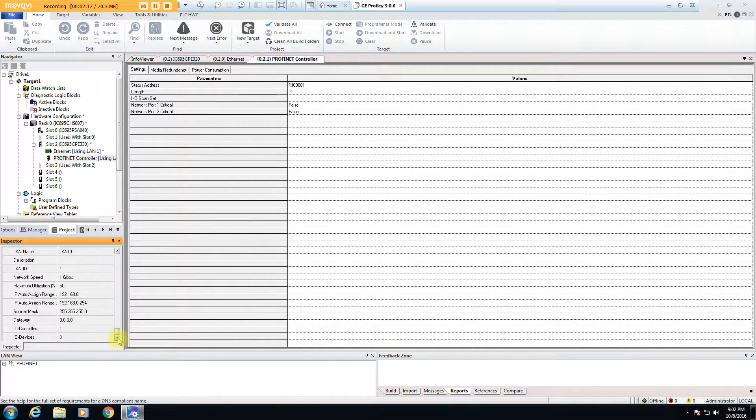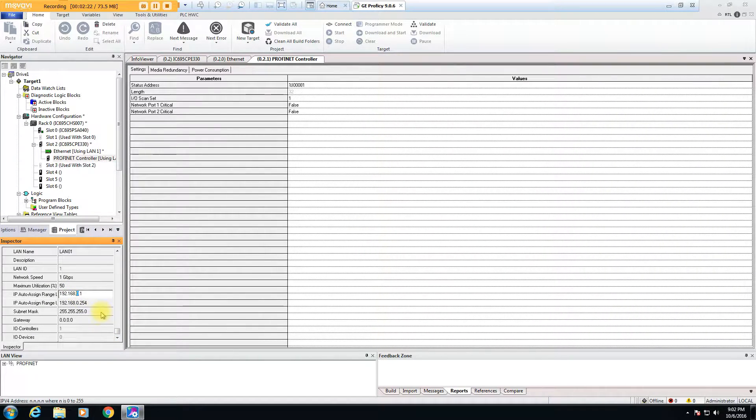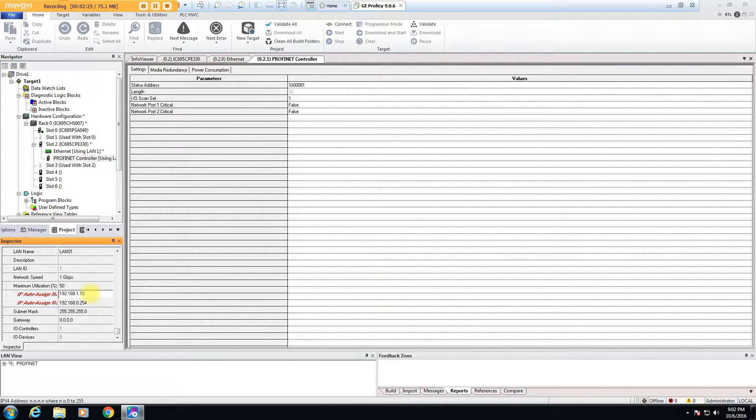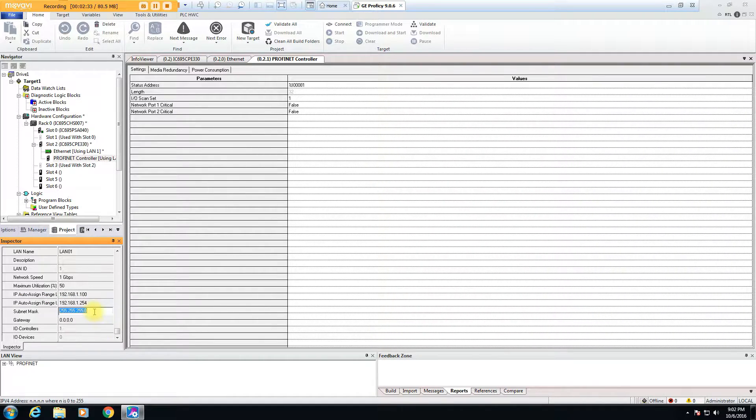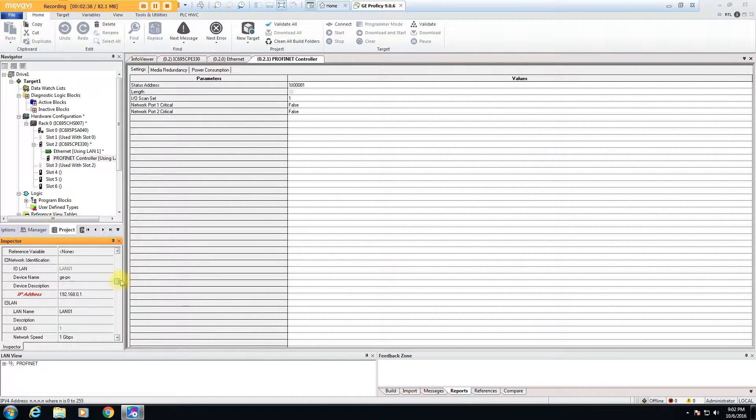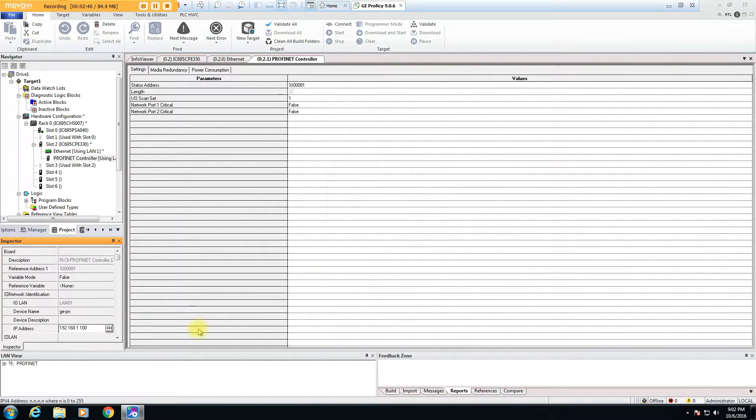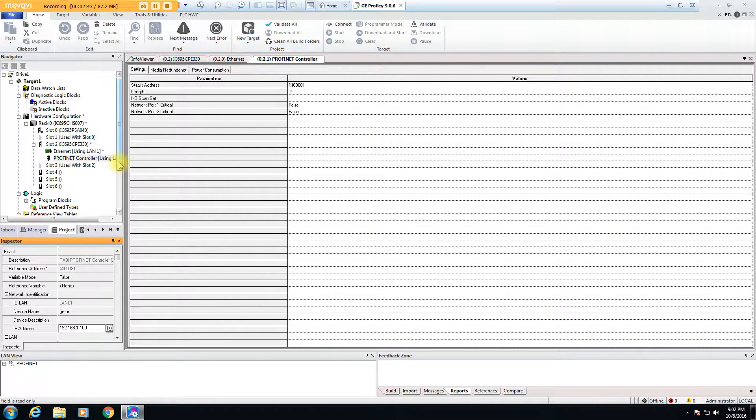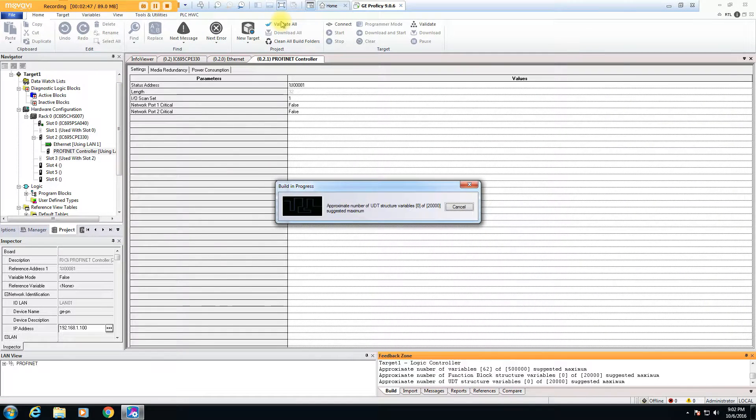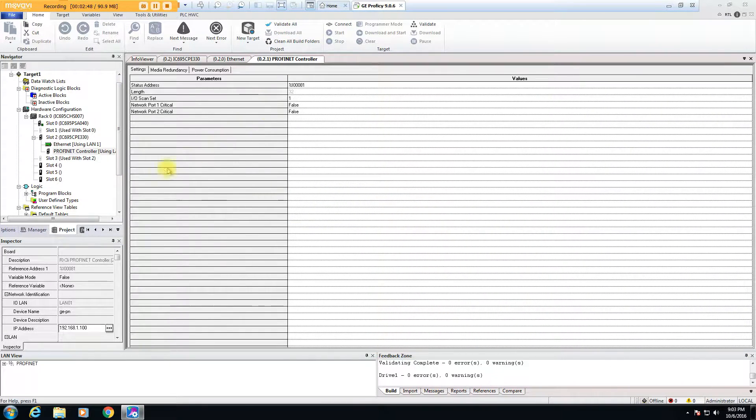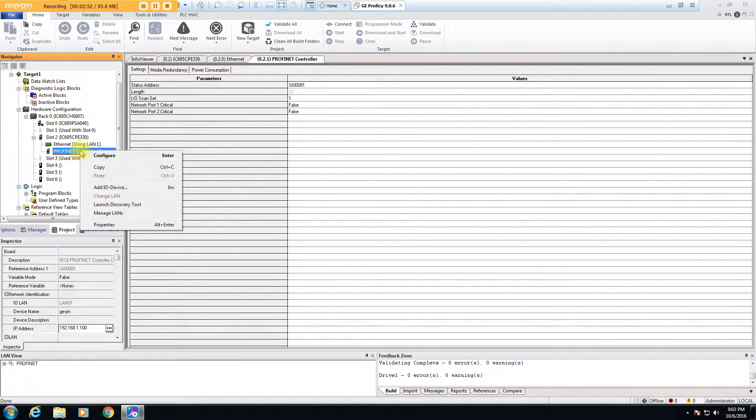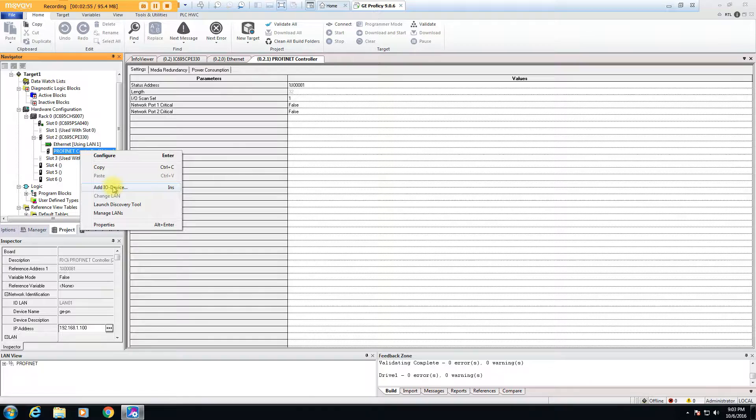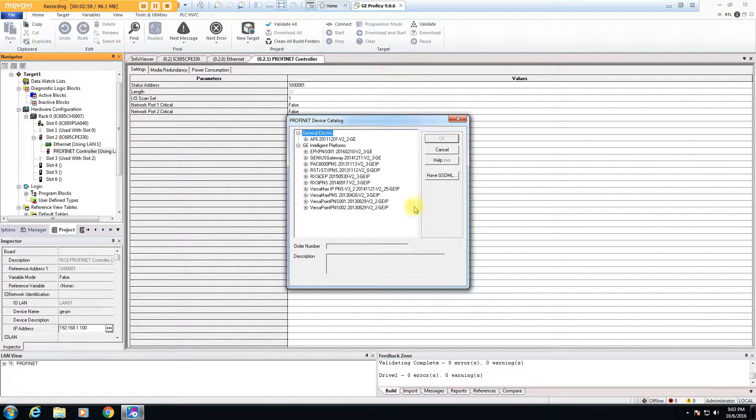On your PROFINET, make sure you set up the PROFINET addresses that are on a slightly different subnet than the main Ethernet port. That's just a requirement of the processor, it's a pretty standard requirement. Even Siemens always wants you to set those as a different subnet, I guess so that it's hard to get confused if you use one switch. You can give your PROFINET ports a unique PROFINET name or just use the default one, doesn't really matter.